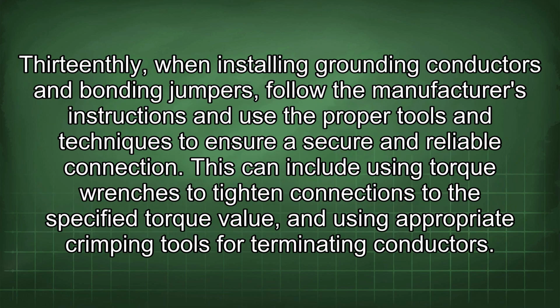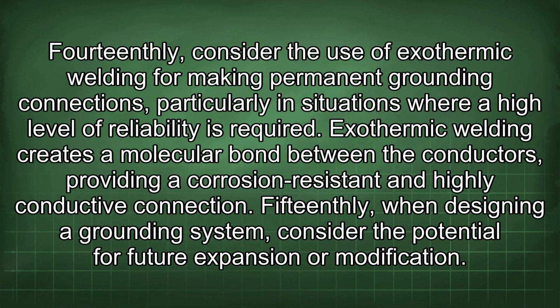13thly, when installing grounding conductors and bonding jumpers, follow the manufacturer's instructions and use the proper tools and techniques to ensure a secure and reliable connection. This can include using torque wrenches to tighten connections to the specified torque value, and using appropriate crimping tools for terminating conductors. 14thly, consider the use of exothermic welding for making permanent grounding connections, particularly in situations where a high level of reliability is required. Exothermic welding creates a molecular bond between the conductors, providing a corrosion-resistant and highly conductive connection.